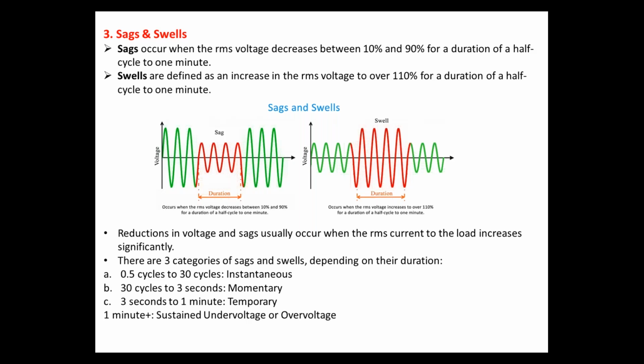The next term is sags and swells. Sag occurs when RMS voltage decreases between 10% and 90% for a duration of half a cycle to 1 minute, this is called sagging. In the voltage sinusoidal waveform, this red color shows where such sagging phenomena occur, a decrease between 10 to 90% for a duration of half a cycle to 1 minute. If the duration is up to 1 minute, where your voltage drops between 10 to 90%, then it is a sagging problem.